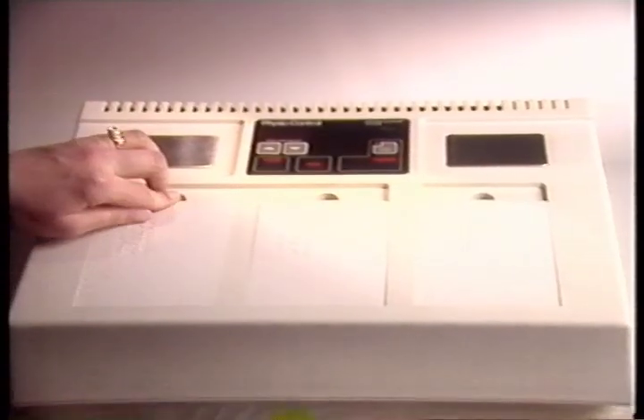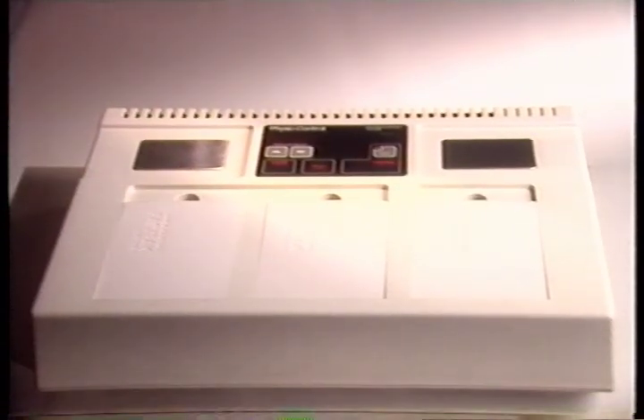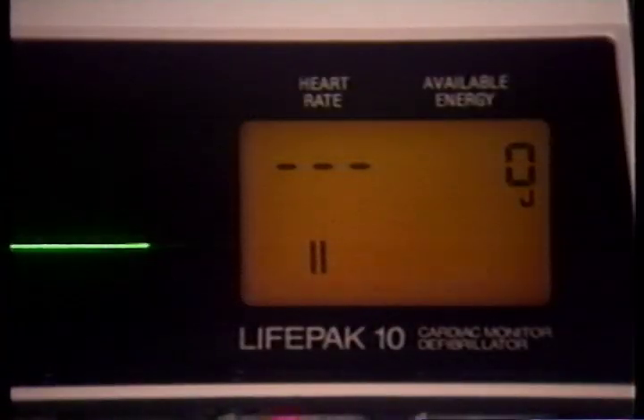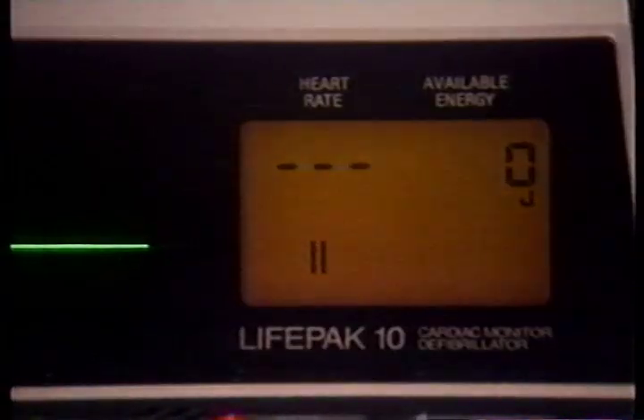position. The nickel-cadmium batteries in your LIFEPAK 10 must be exercised and maintained. Your Physio Control battery support system can be used for both charging and exercising your battery packs. Proper battery pack maintenance can be very important to the operation of this instrument. Therefore, you should consult your operator's manual to obtain the necessary information on proper care and maintenance of NiCad batteries. From the factory, the LIFEPAK 10 powers up in lead 2 with an ECG gain of 1 millivolt per centimeter.